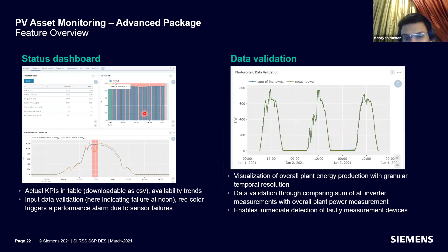Regarding the digital twin, it's all about what-if scenarios. Ideally, what if your solar panels are delivering to the maximum? When a solar plant is installed, clean and new, it can generate around 1,300, that's the expectation, based on experience. What was actually measured on site, shown by the blue line, was around 1,000 kilowatts. After cleaning and correcting the error, whether an inverter error or a soiling loss, generation obviously increased.